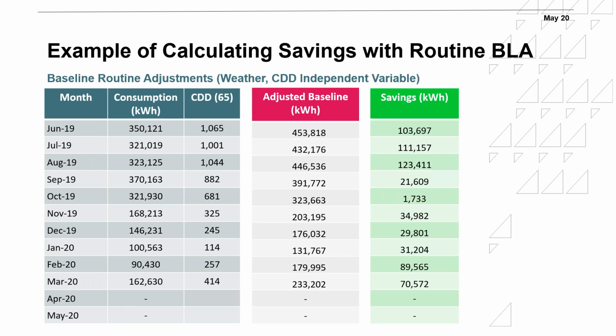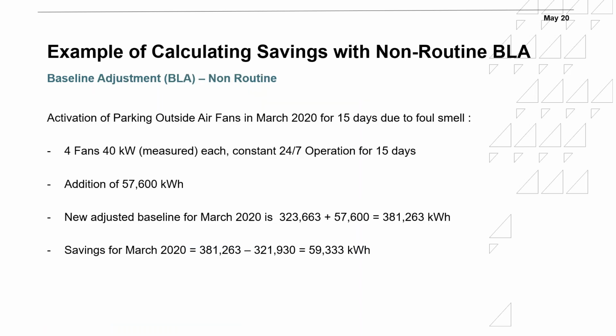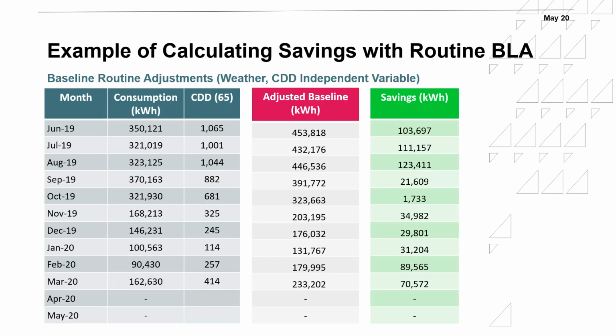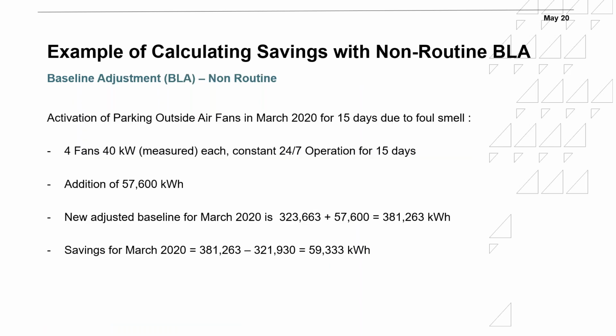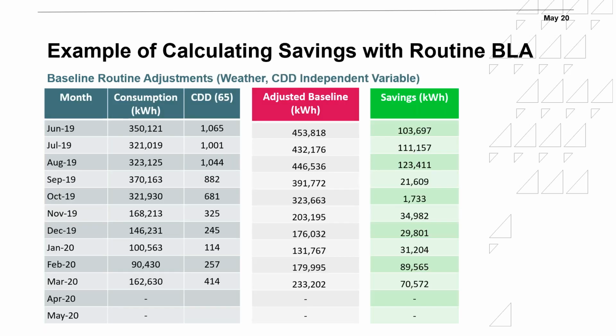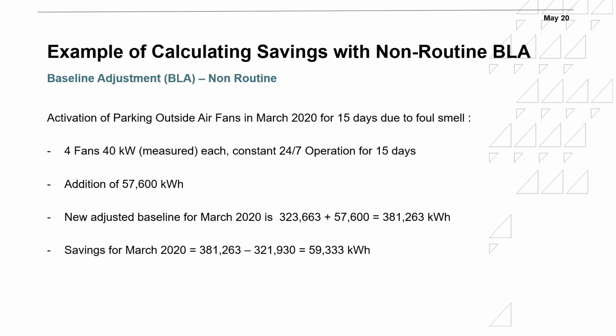In that particular case, the change was basically what we call a non-routine baseline adjustment. What we've done with the weather is a routine baseline adjustment based on an independent variable, which was the cooling degree days. Non-routine is something that we really don't expect to happen, but it did happen. In this case, for October, what happened, yeah, it's actually instead of March, this is a typo, it should be October. So what happened here in October 2020 is that for 15 days, they ran their parking fresh air fans.